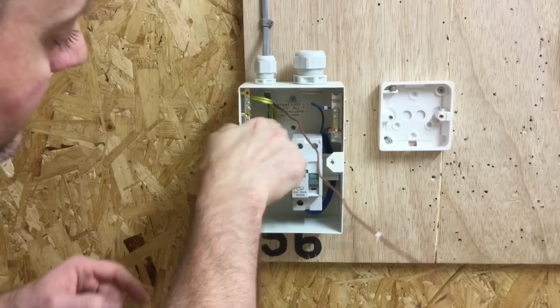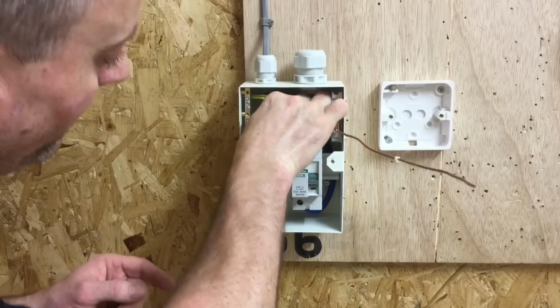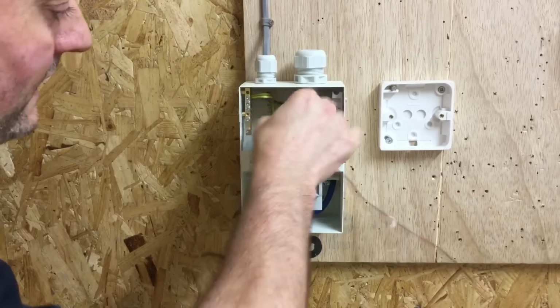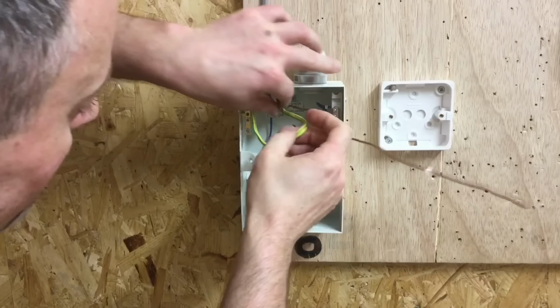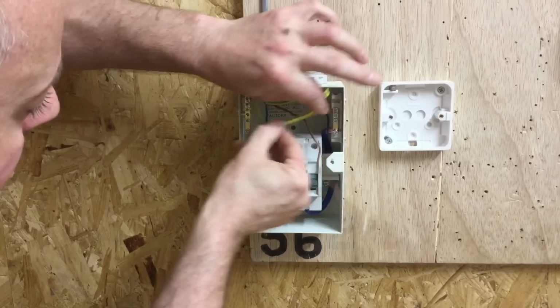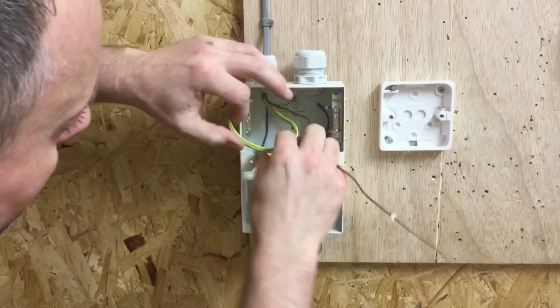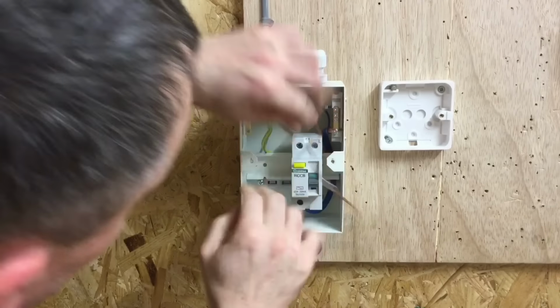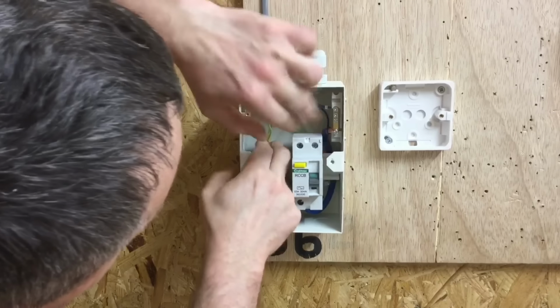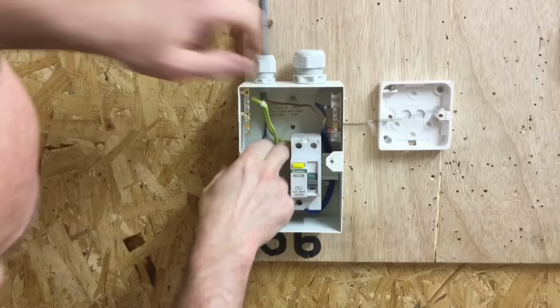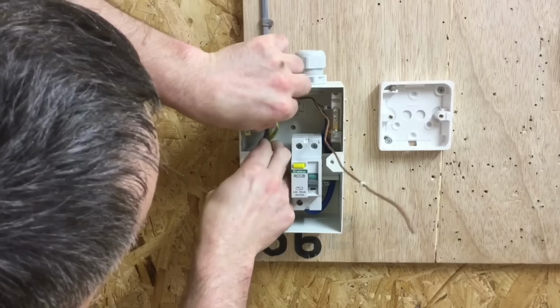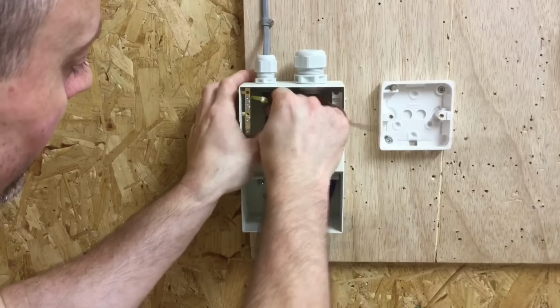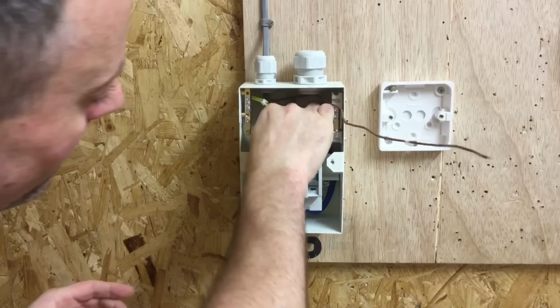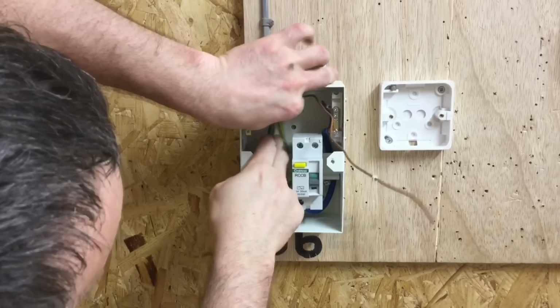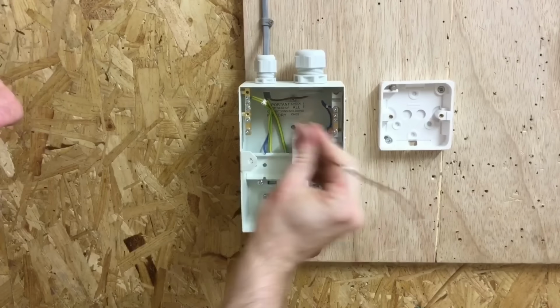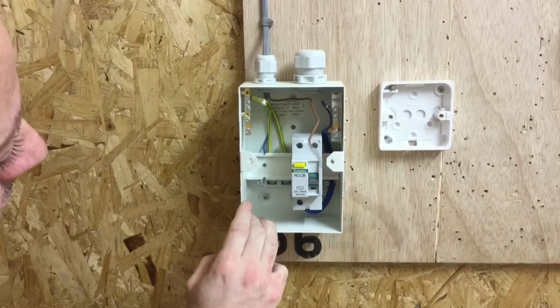Got to make sure we can see our number one, which has fallen back a little bit. So I am going to just bring that back round. So I take it back out again, move the number one closer to the termination position. Apologise. And so we can see it there at termination, and then poke it back in again. And dress it hopefully straight down, and then straight back up again. Okay. So there we go. I'm going to have a little fiddle with that before I go on to look at the connection for the line conductor and fitting the circuit breaker as well.